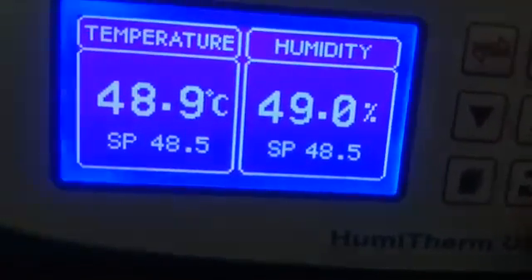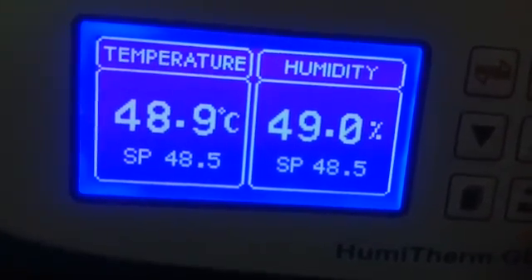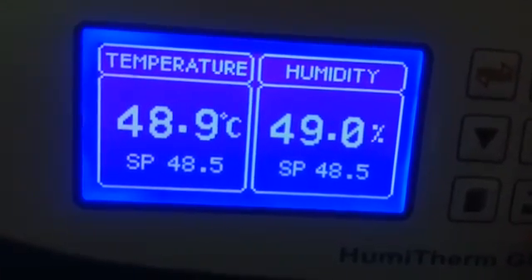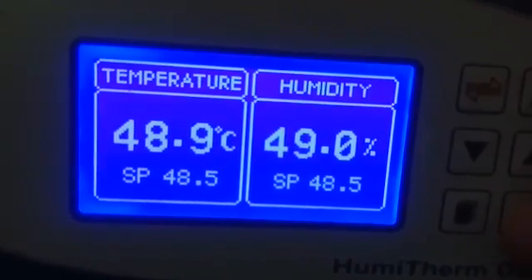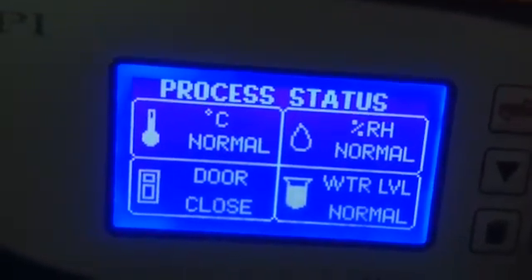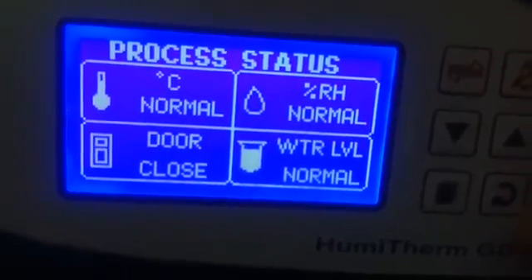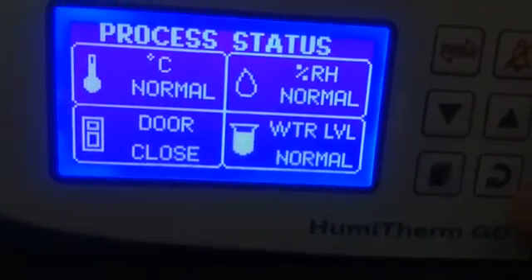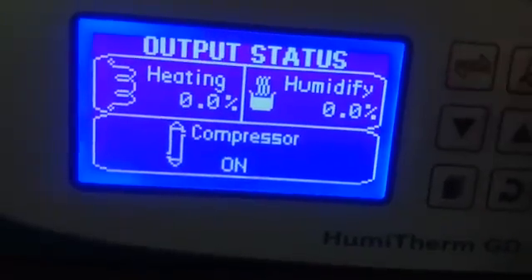This is the temperature and humidity display. Temperature set point is 48.5, process value is 48.9, humidity 49.0, set point 48.5. If you press the information button, you can see normal temperature status. If it is within the set limit nearby, temperature is normal, %RH normal, door close, water level normal.